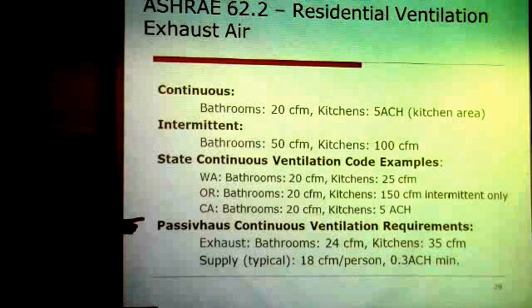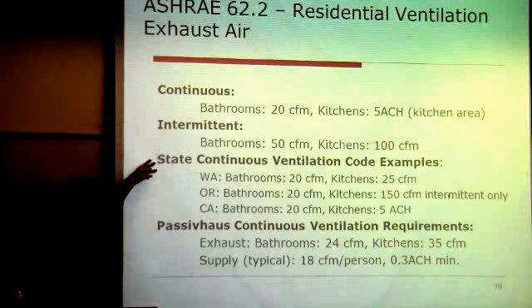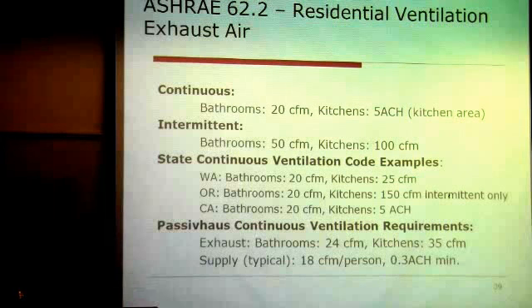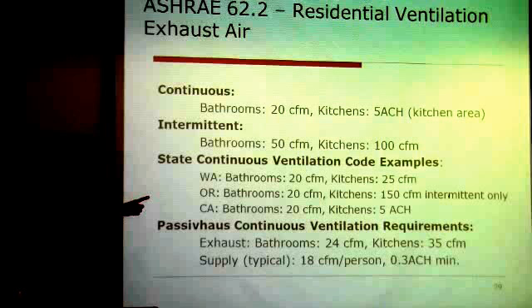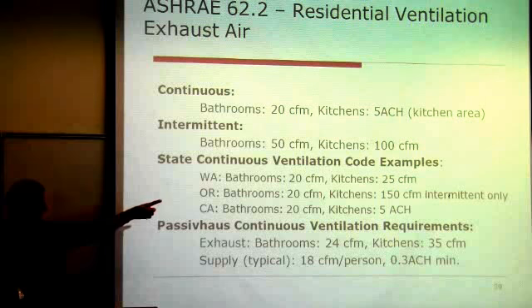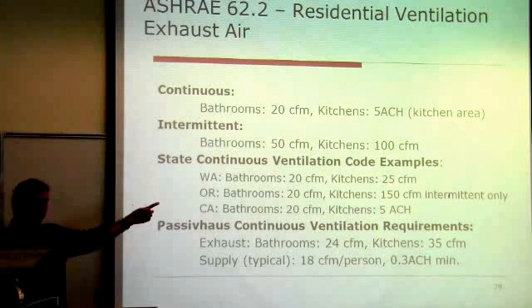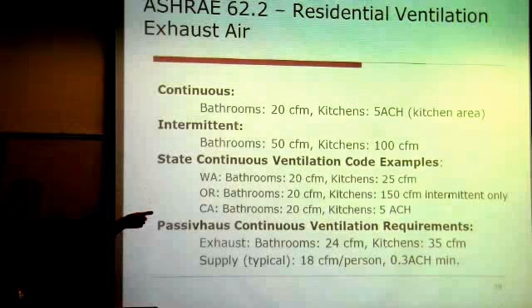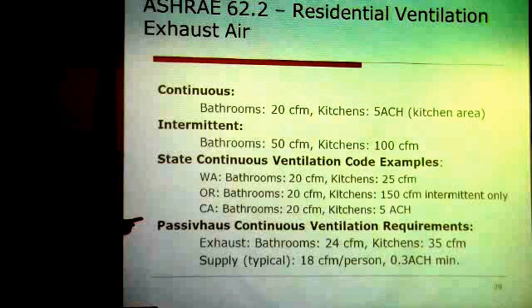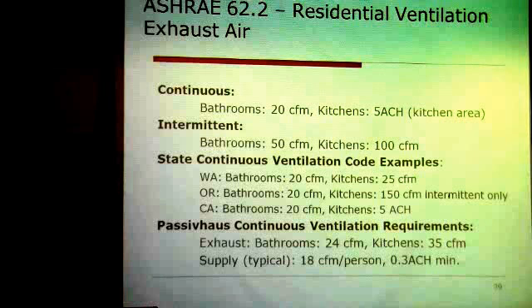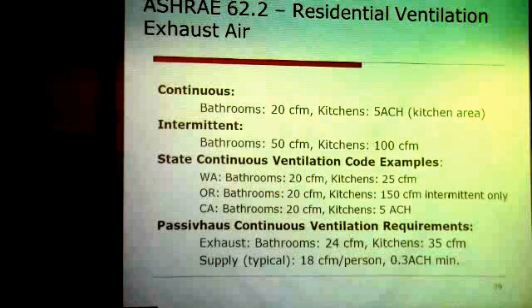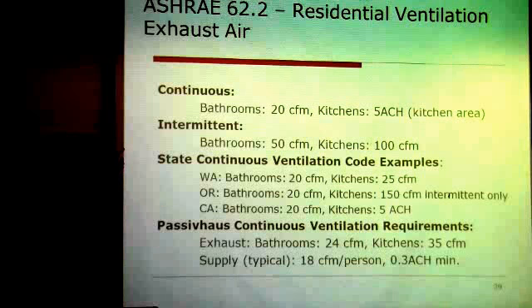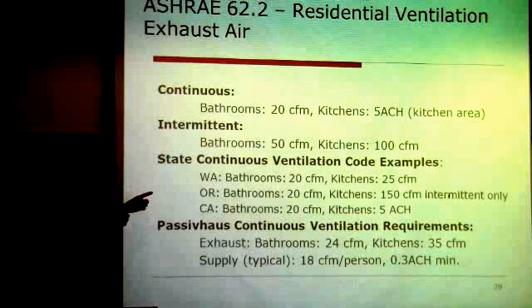Different building departments will have different requirements though. For example, the state. If you look at the different states, Washington, Oregon, California. In Washington, bathrooms are 20, and then the kitchens are 25 for continuous. Which is, I think, from the International Building Code, which deviates from the ASHRAE. So there's different codes out there. Some building departments follow ASHRAE, some changed it a little bit.